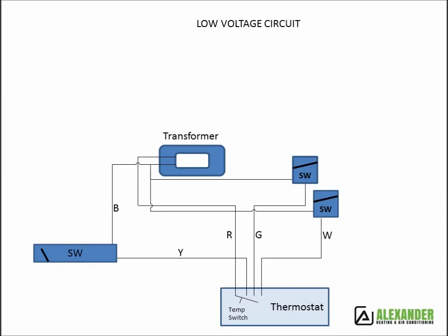The low voltage circuit has two modes. Let's look at the AC mode. In the AC mode, the thermostat sends the signal in two directions. The Y wire turns on the outside fan and compressor. The G wire turns on the indoor fan.